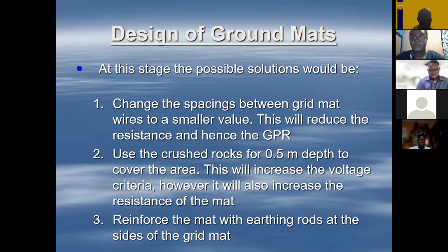We can accept the crushed rocks from the contractor. If you put that in, it means it will now increase the tolerable touch and step, because it brings in a higher Cs value. So you get that multiplier effect, because the tolerable touch and step will increase.